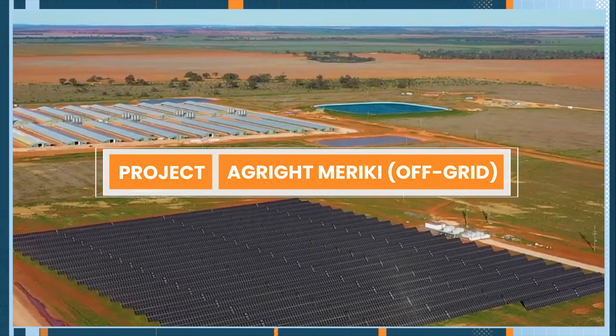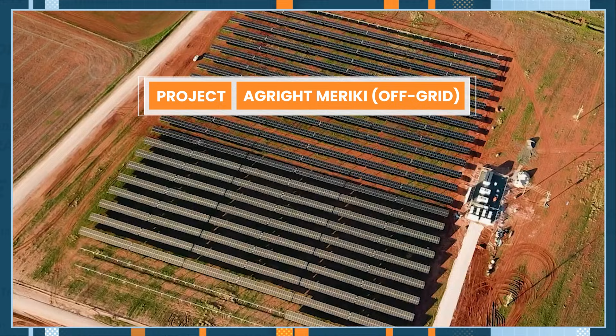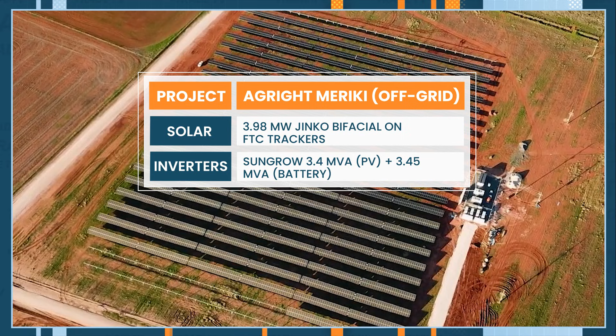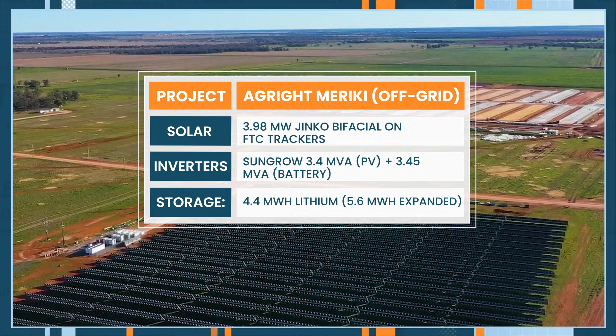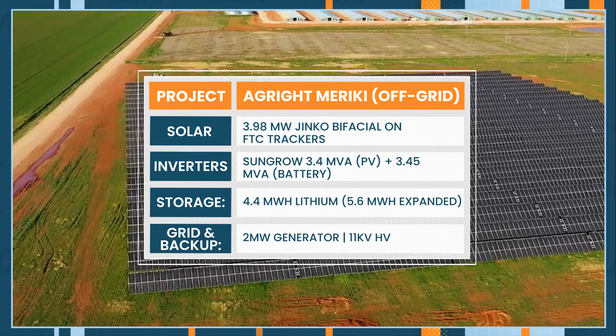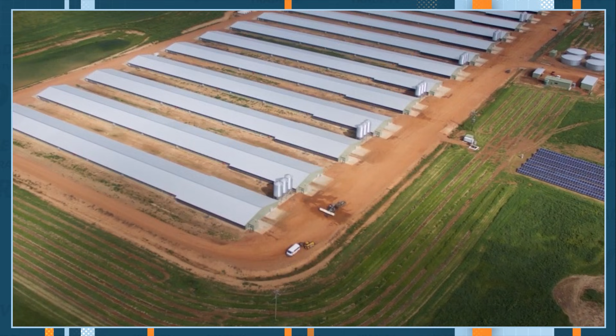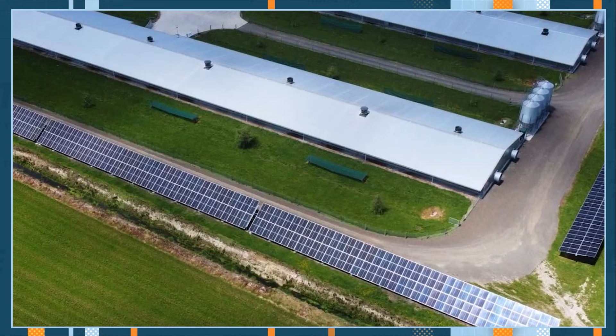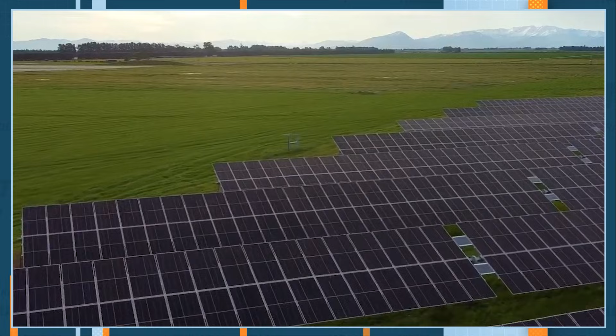We call this project Agright Meriki, named after the customer Agright, a chicken farming company for poultry meat, and Meriki, the name of the farm. This project is a 4 megawatt solar tracking system feeding a centralized power station with 4.4 megawatt hours of lithium storage and 2 megawatts of diesel generator backup, feeding out through an HV main about 3 kilometers to supply 40 chicken sheds, water pumping, water filtration, and 6 homes across a very large piece of land. It's 100% off grid and will soon be connected to the grid. Since installing it originally, we added another 1.2 megawatt hours of storage, so we're now up to 5.6 megawatt hours, and it is the largest off-grid farm, I believe, in the world.